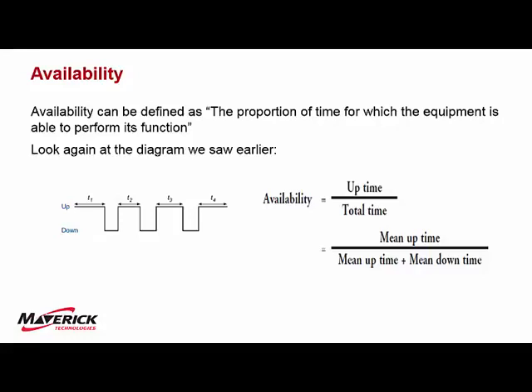Another term is availability. Availability is how often is it working. It's the proportion of the time that the equipment is able to perform its function. All of the T's added up over all of the time together. Mathematically it's kind of simple. You may wonder why are some of these downtimes longer than others? How long does it take to repair something that fails? Part of the problem is you may not realize it failed. Availability is not the same thing as reliability. Reliability is strictly mean time between failure. How long will it run? If you have a cheap pump but that pump is pumping every day, you'll know as soon as it's down and you'll fix it quickly. So its availability is going to be high because it'll run, you'll break it, you'll get it right back running again, but its reliability might be kind of crappy. They're not exactly the same thing.